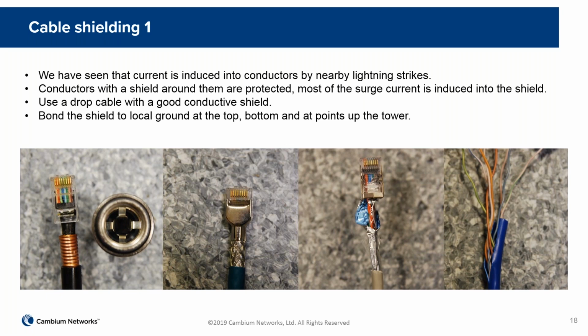Then we have a cable which uses a foil screen and a drain wire. I mentioned earlier that the currents we're looking to intercept here are in the hundreds of amps. Our foil screen is an aluminium screen. Generally speaking, it has an oxide layer on one side, and on this one you can see that there is a blue plastic coating on the other. And then we have a drain wire which is associated with it.